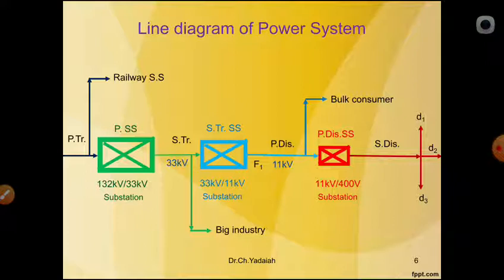Before the DTR, the input is known as feeders. After the DTRs, we call them distributors. The feeder is designed for a predefined current rating of the line, and there is no tapping in between. Whereas the distributor takes a number of tappings, and it is mainly designed based on the voltage drop of the line. These things you should know.